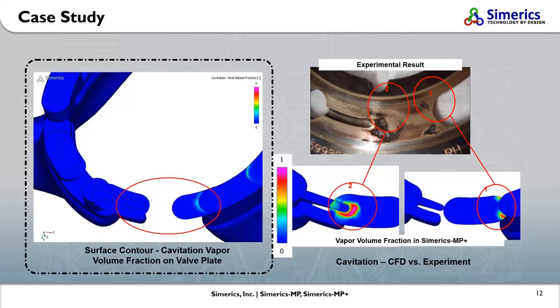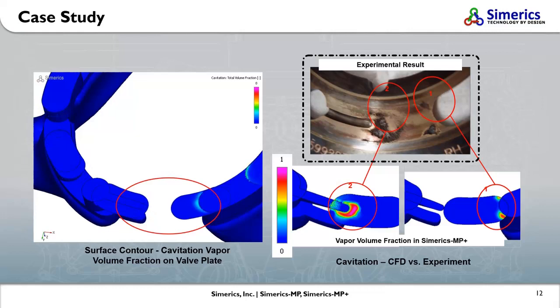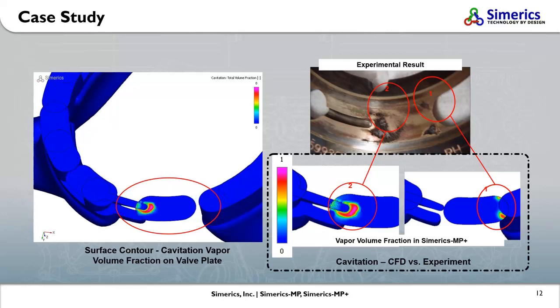This constant formation and collapse of bubbles can occur thousands if not millions of times over the life cycle of a product, and will cause significant erosion on metal surfaces especially. The image at the top right taken after an experiment confirmed this prediction by showing significant pitting and erosion at the same locations on the valve plate.